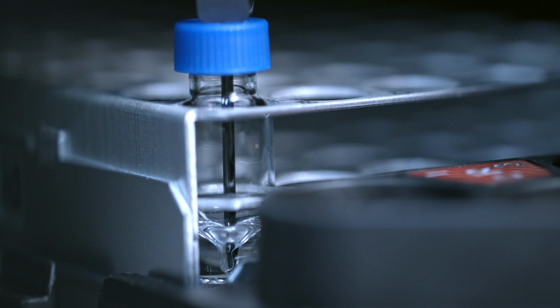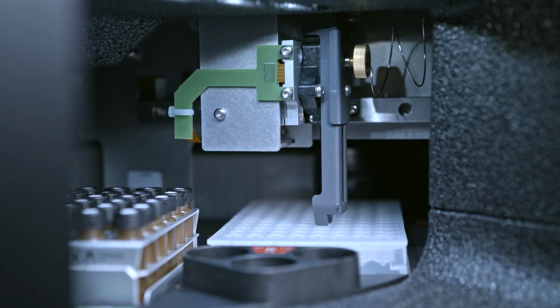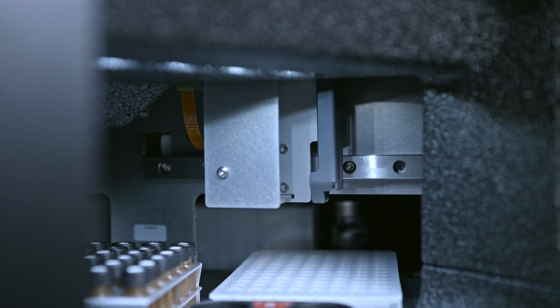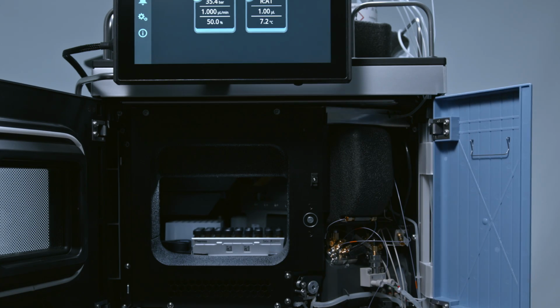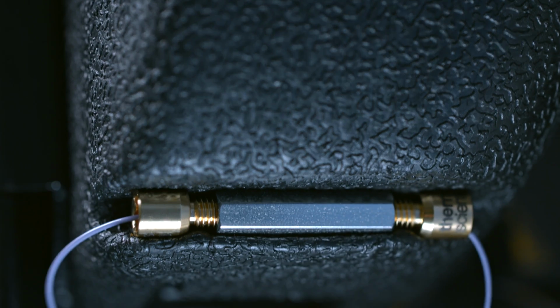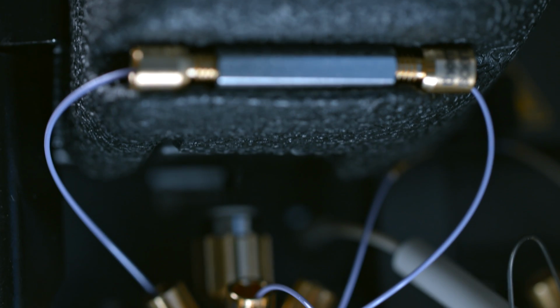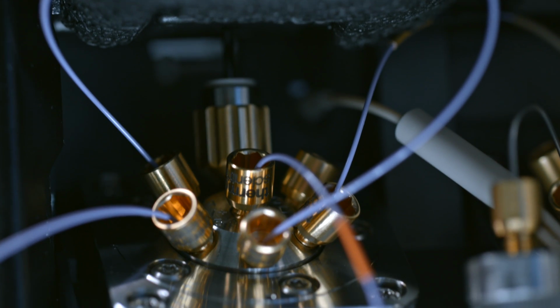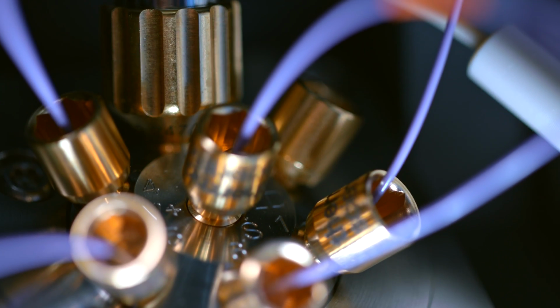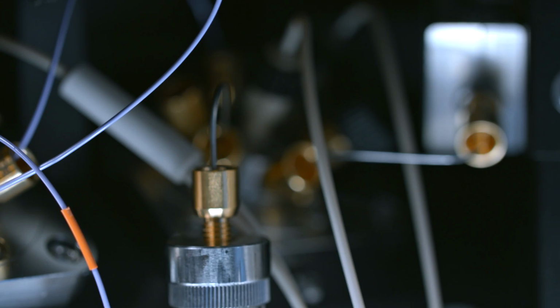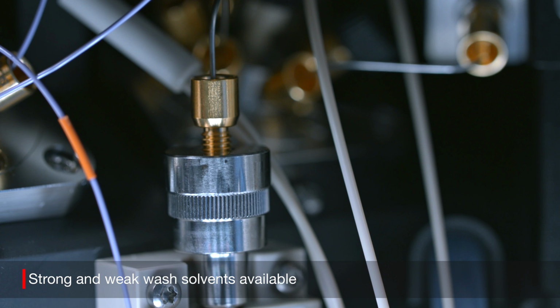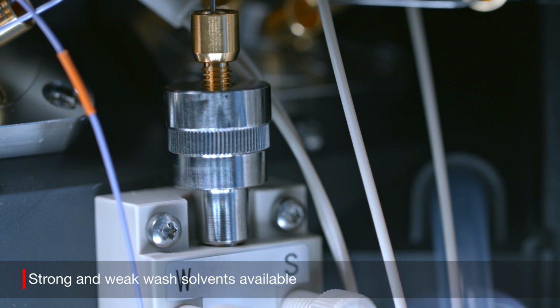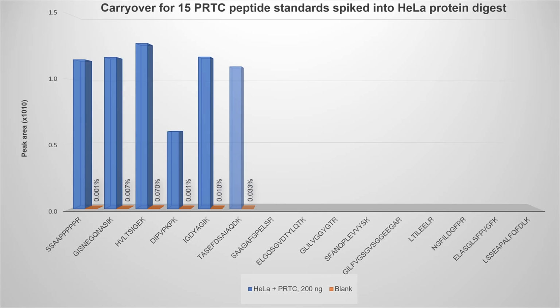Combined with the vial bottom detection technology and the split-loop autosampler design, the Vanquish Neo UHPLC system maximizes the usage of valuable sample. During the injection, Smart Inject technology significantly reduces the pressure drop for direct and trap-in-elute injections, increasing flow consistency, improving retention time stability, and extending column lifetime. Automatic wash procedures guarantee minimal carryover for the highest quantification accuracy.